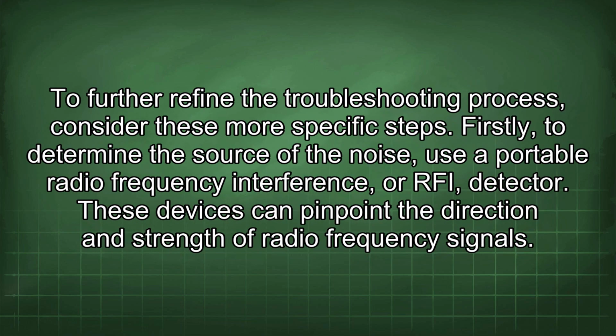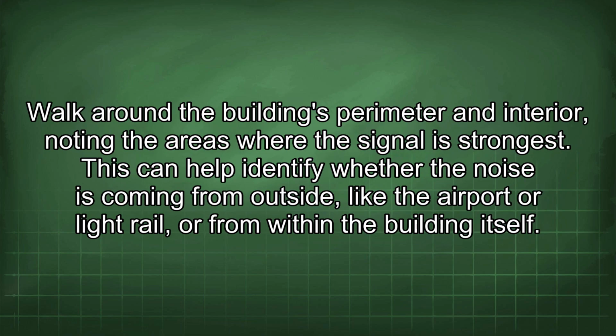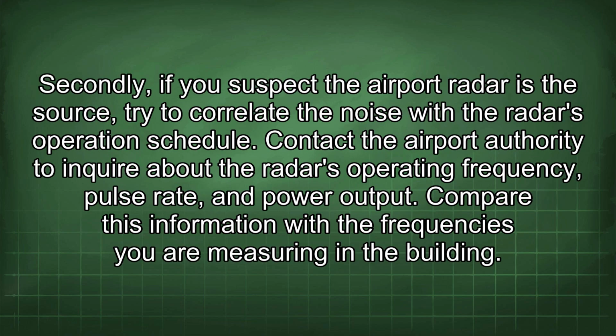To further refine the troubleshooting process, consider these more specific steps. Firstly, to determine the source of the noise, use a portable radio frequency interference or RFI detector. These devices can pinpoint the direction and strength of radio frequency signals. Walk around the building's perimeter and interior, noting the areas where the signal is strongest. This can help identify whether the noise is coming from outside, like the airport or light rail, or from within the building itself.